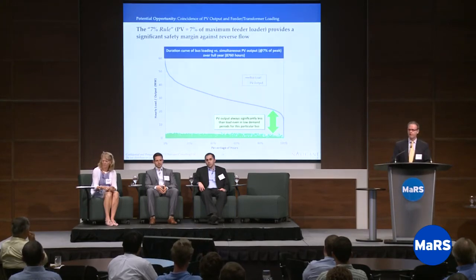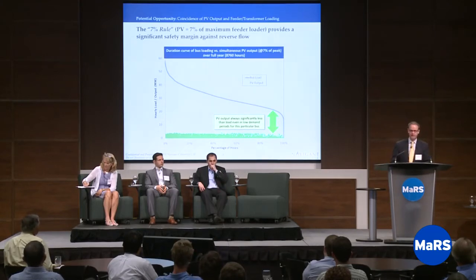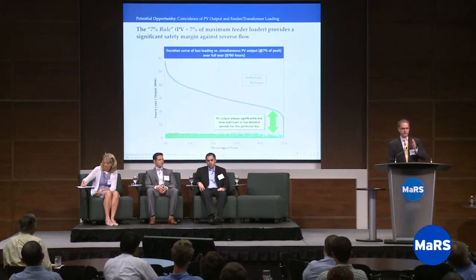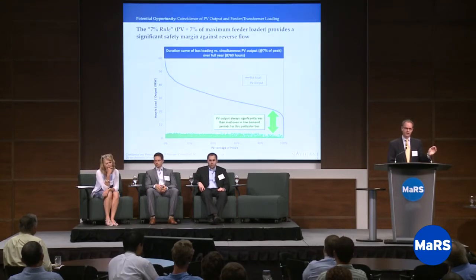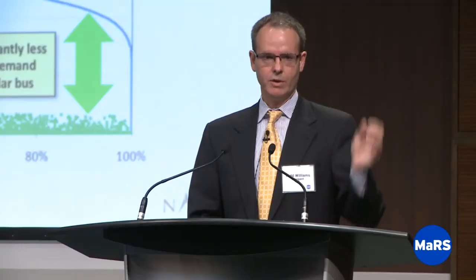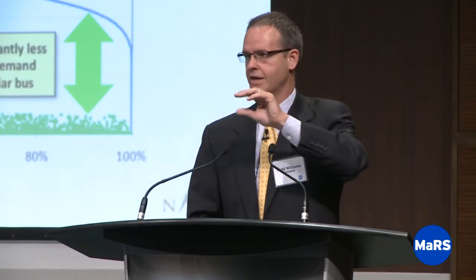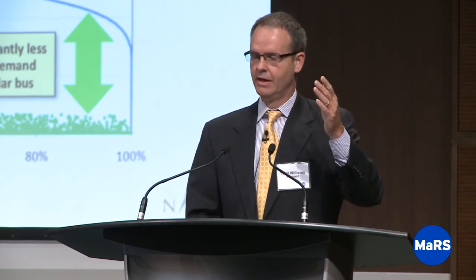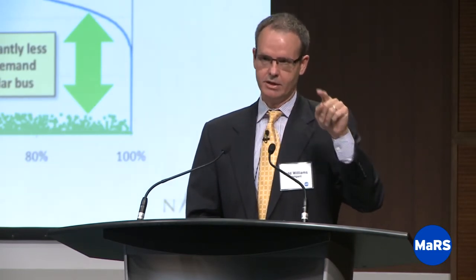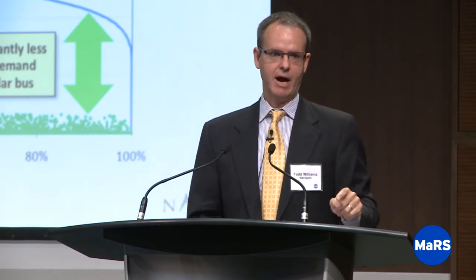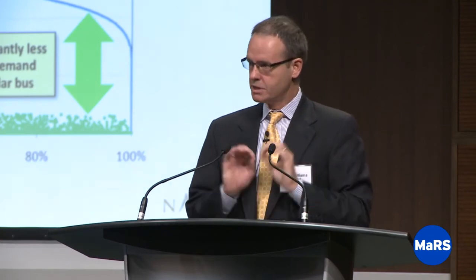So if we look at, I've referred to the Hydro One 7% rule. The PV cannot exceed 7% of the maximum loading on the feeder. So what I took is we have different feeder information for all hours of the year, 8,760 hours, and I sorted that from highest to lowest. So at say this hour today, that might be halfway down that curve, and we had a simulated PV output given the weather, and I think this was 2009 data we used. So we sorted the transformer load. This is a bus load, which is actually an aggregation of feeders, but just imagine it's a feeder. We sorted the load from highest to lowest, and we looked at the predicted solar output at that particular hour, and that's all the green spots on the bottom.